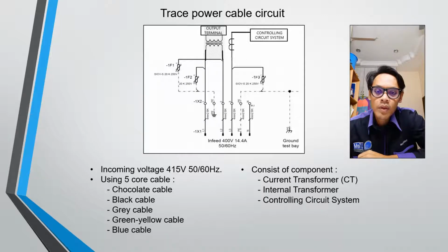From the power terminal block, 2 lines will be distributed to the internal transformers and 1 line will be distributed to the current transformer, CT. The internal transformers of the frequency converter have the capability to provide a variable voltage from 0 volt until 400 volt. The current transformers are used to reduce the amount of current to a very low current because it will be used for the controlling circuit system inside the frequency converter.